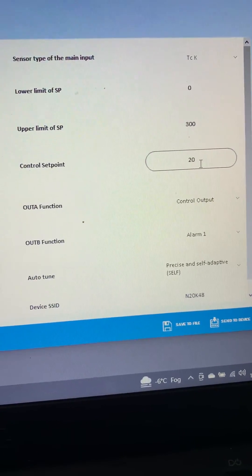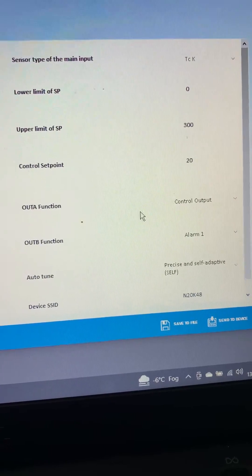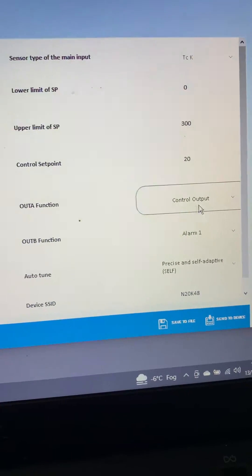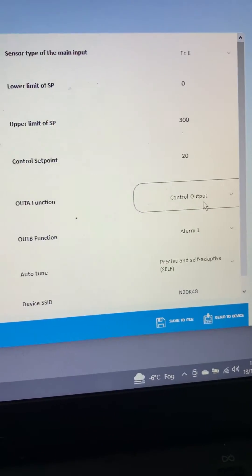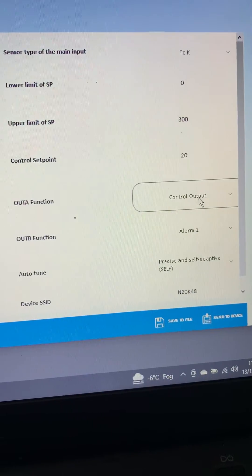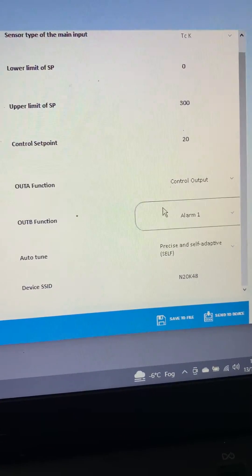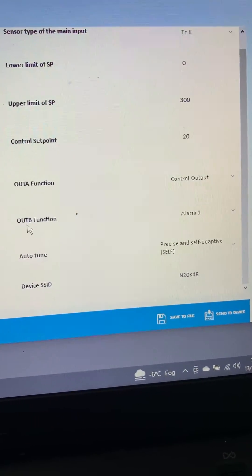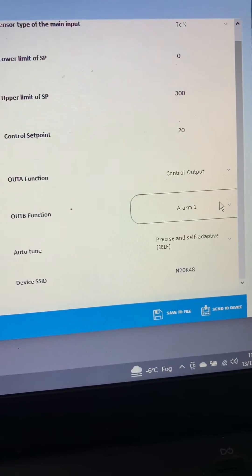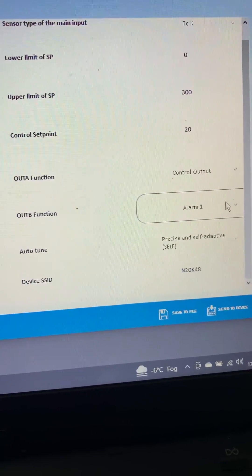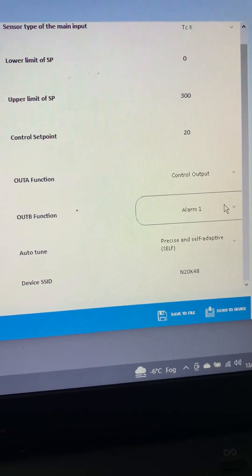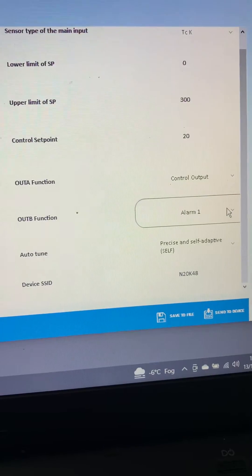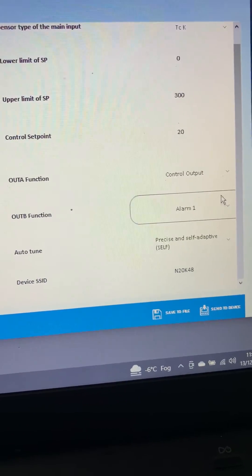The main set point we've just set out to 20 degrees for now. Output A, that's your control, so that's going to go to the solid state relay for heating. Output 2 or output B, that's an alarm, so the relay is going to operate and we're going to use that to cool the process down at the back end of the program, basically help it to reach room temperature quicker between cycles.